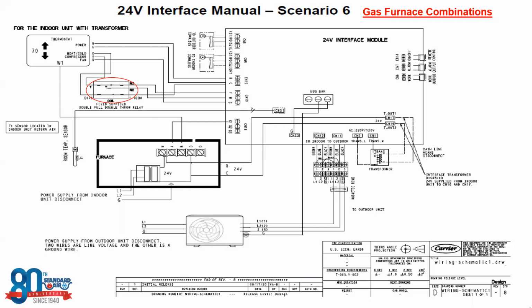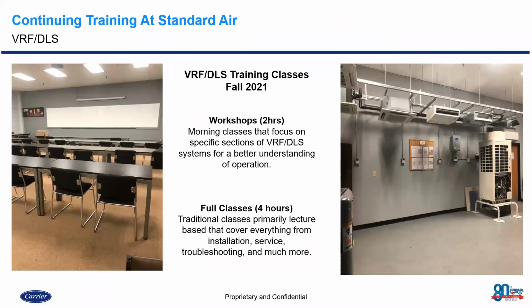Okay, so it could be a little bit confusing on how we're doing everything, but essentially the relay is going to allow the different changes depending on what mode that we need to be in. Are we going to send a control signal for cooling or for heating for the heat pump? Or are we going to send a control signal for heating directly to the gas furnace, depending on what system that we want to run? But in essence, aside from that field supplied relay and setting the thermostat up as a heat pump or a dual fuel thermostat, we're essentially doing the same thing as we did wiring wise with the FV4. The only difference is now we have a gas furnace versus electric heat, which we know is going to be a lot more efficient. So that's what I had for you guys.